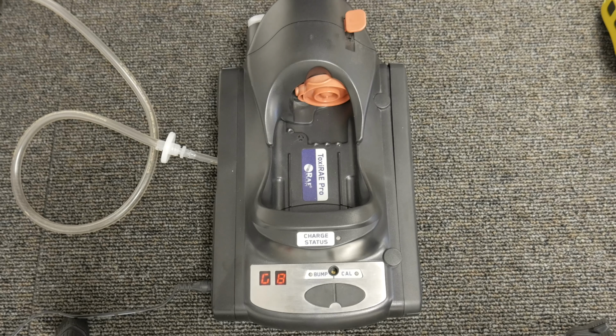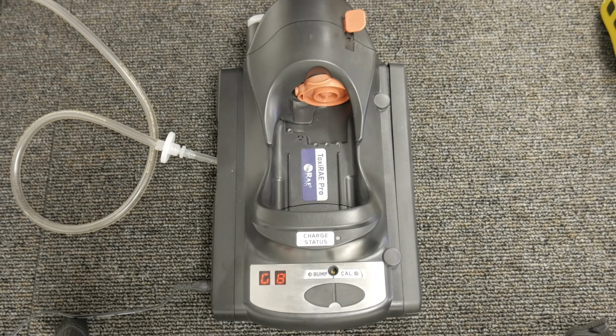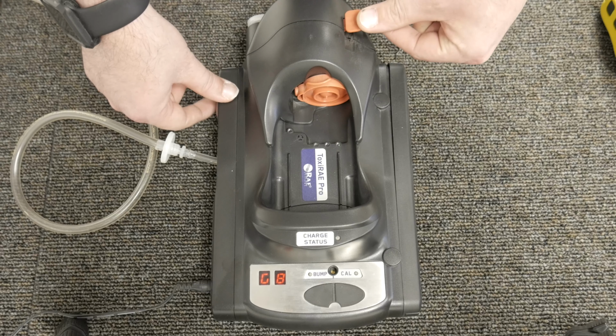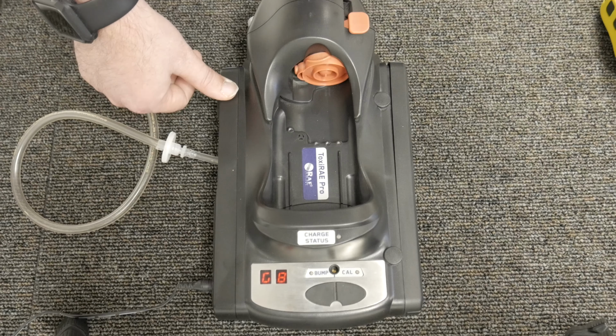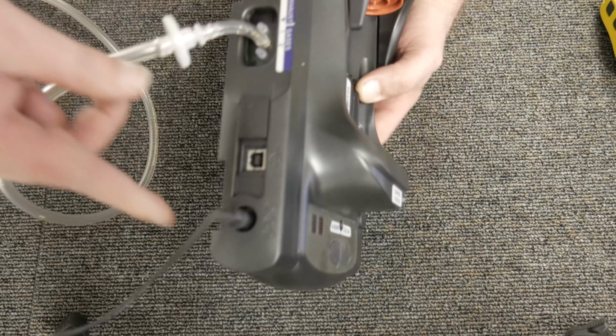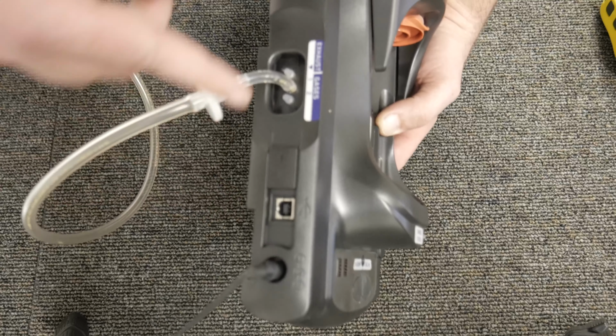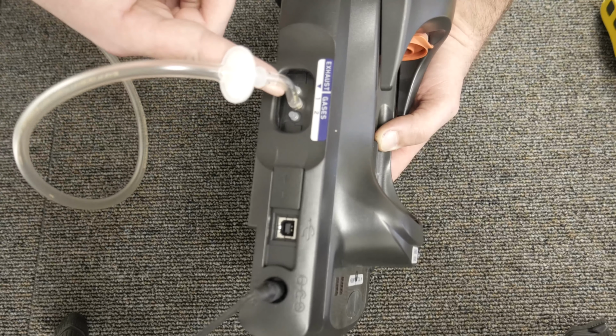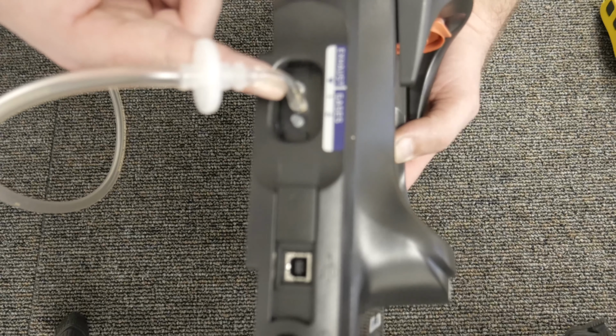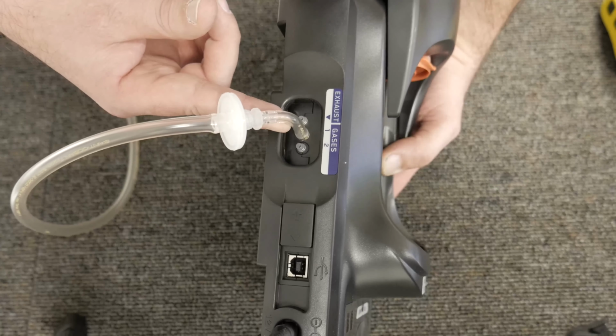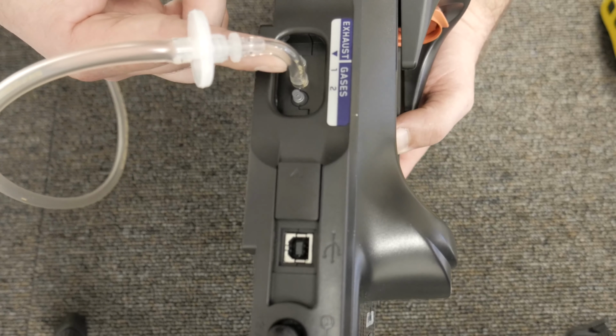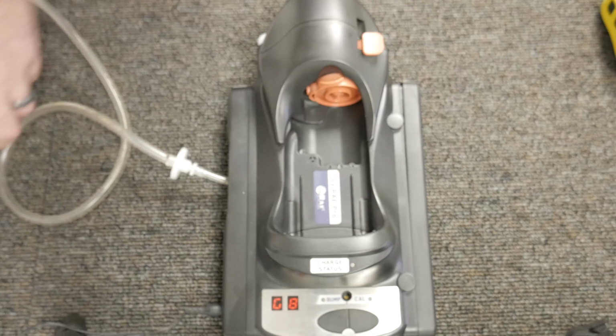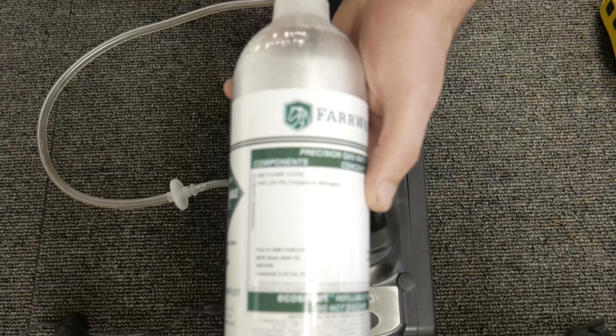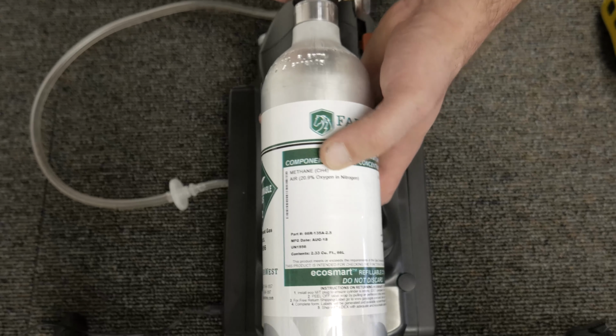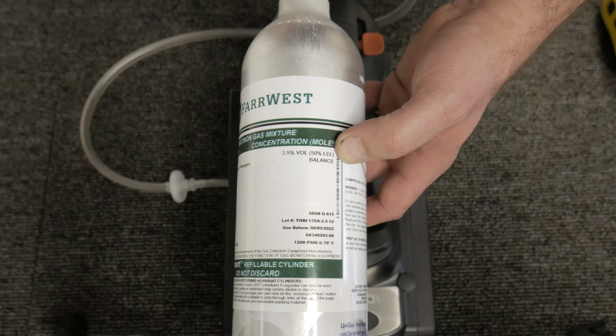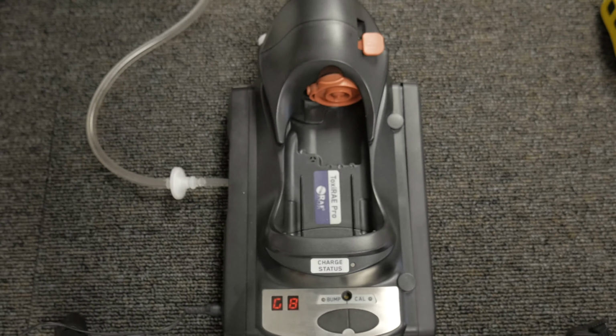Here we have the ToxiRAE Pro cradle. It's a very simple operation. To unseat the unit, there's a lever on top that you can unlock it. We also want to make sure that you have constant power plugged into the unit, and also that your gas is in the gas inlet number 1, as you can see here. And for the gas, you want to make sure that you have a bottle of methane or CH4 at the 2.5% by volume or 50% of the LEL.